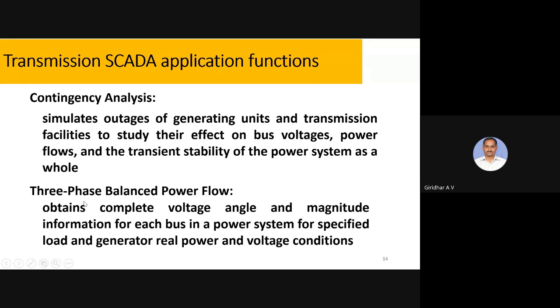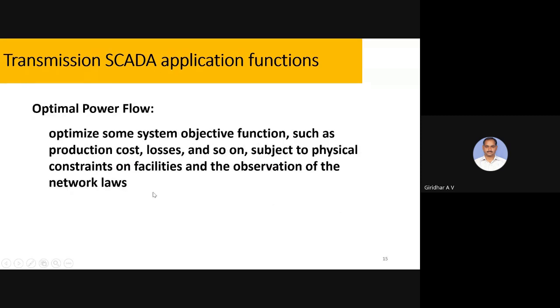We can also do contingency analysis and transient stability studies. Even three-phase balanced power flow, complete voltage angle and magnitude information, we can get. Even now, intelligent electronic devices with phasor measurement are used. Synchrophasors through GPS time stamping can all be done simultaneously, and these features are nowadays added in the devices. Then optimal power flow.